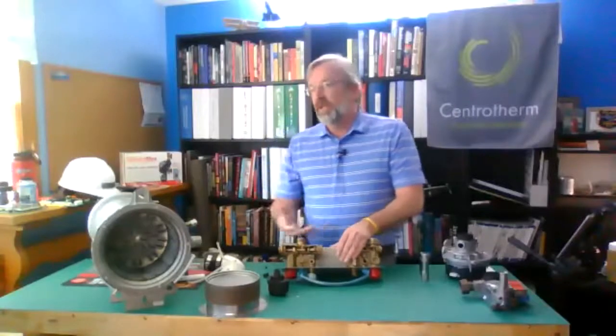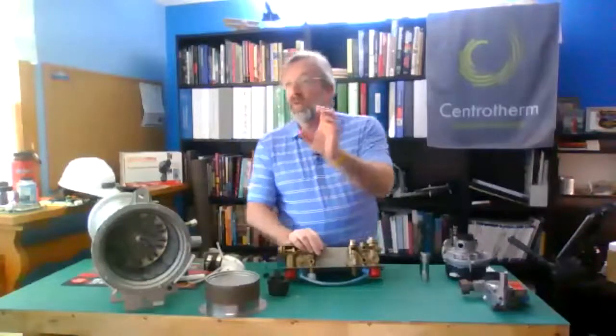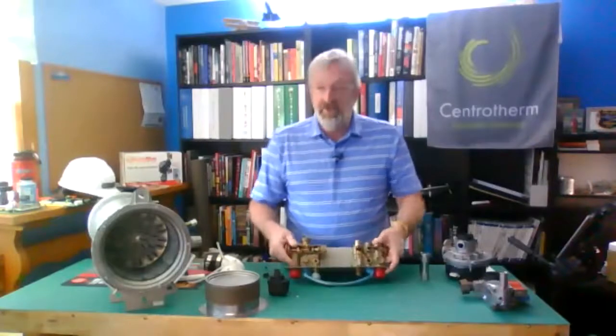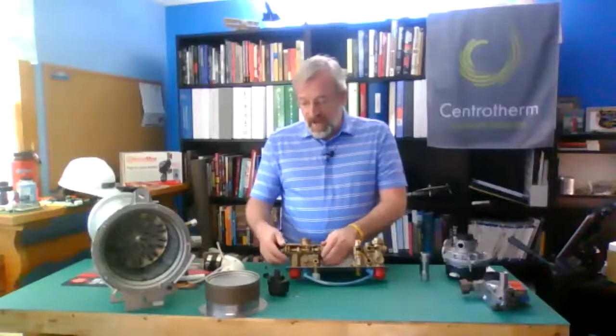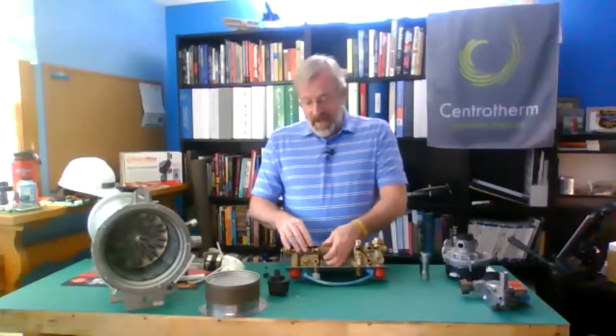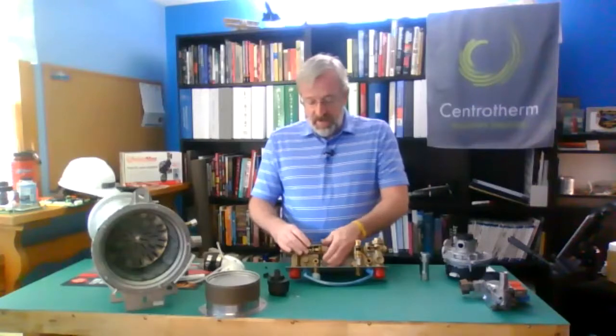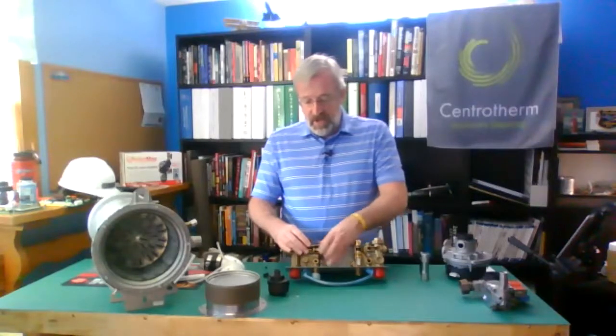So red light, icon, diverter valve diverts. Diverter valve doesn't divert. Let's make sure we're getting the 24 volts. And then we just trace that back up through to there's actually a specific board with a relay on it specific to that diverter valve. So pretty simple. If you did have to clean this side of it, first of all, you're going to get wet, but it's, again, pair of channel locks. Just be nice and easy to it, and you can unscrew that and take it out. Just remember, you're going to get wet when you do that. And then if you clean it.